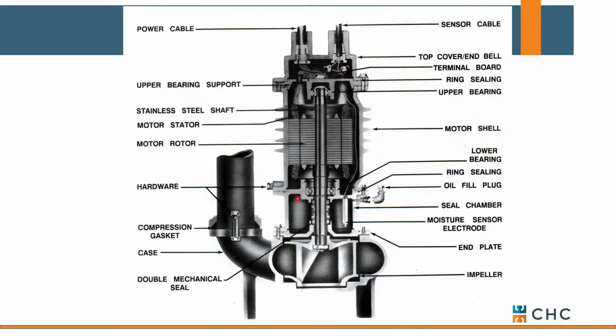Okay. You'll also notice that we have a seal chamber. This is a little unique in that we've got a seal chamber running in an oil bath, basically. And there's also a moisture probe that sits in there. If one of the seals fails, we pick up moisture on the probe, and this gives us a signal back at the control panel that we've got a pump in need of service, and it will actually take it out of rotation. It's how you monitor a pump that's below a body of water and out of sight. It's one of the protectors or safeties here.